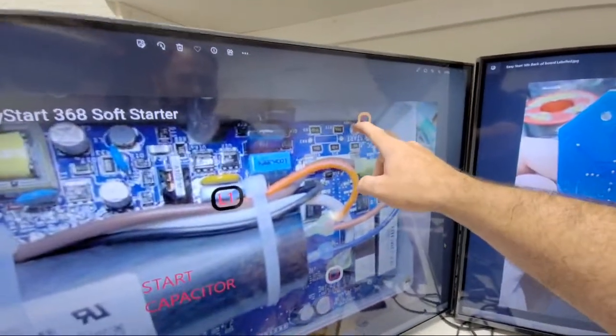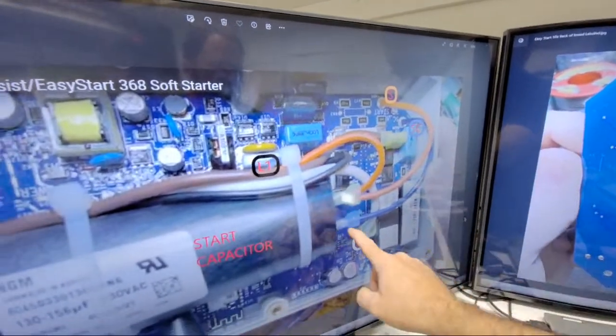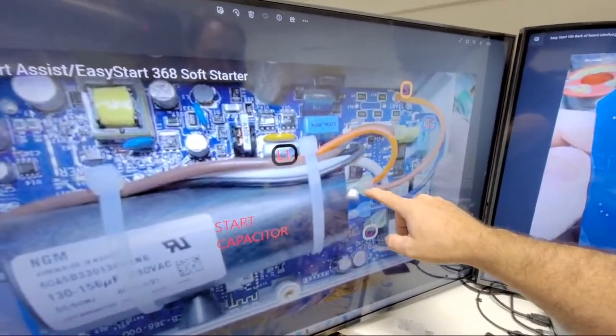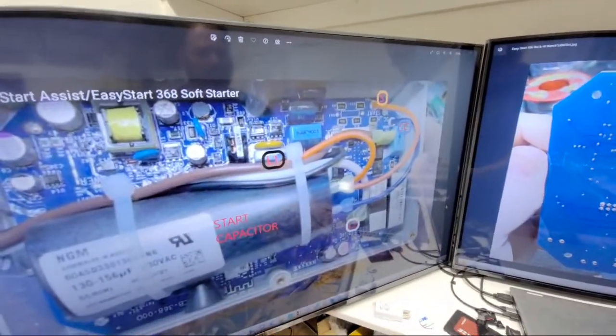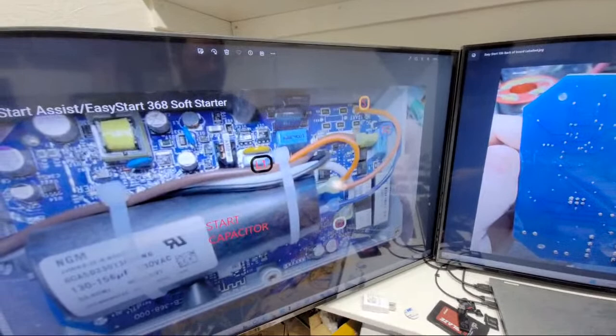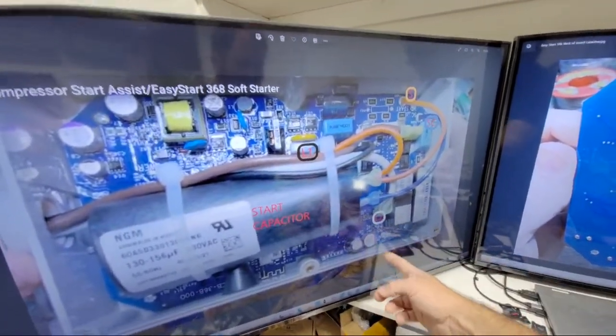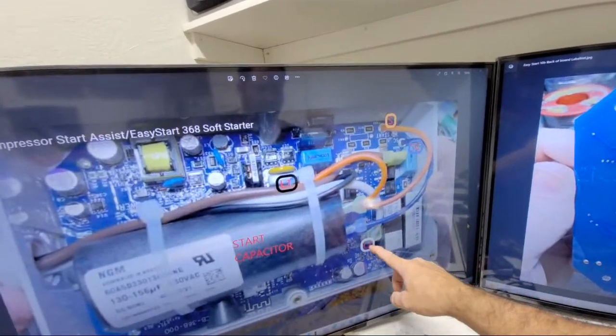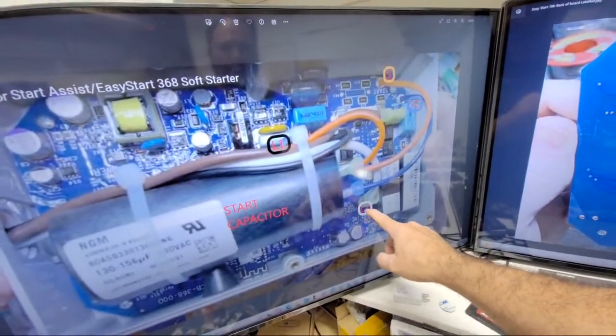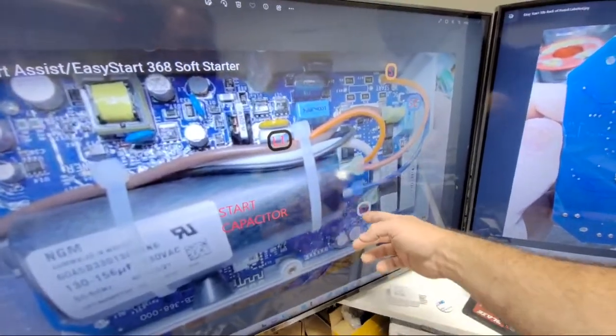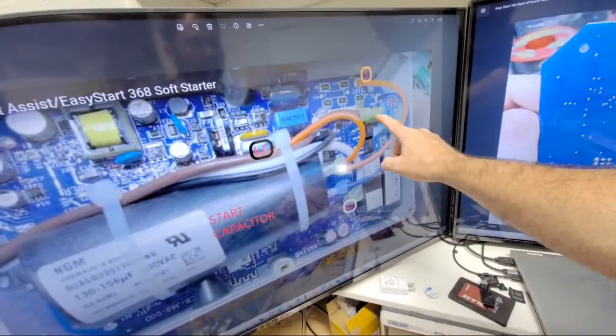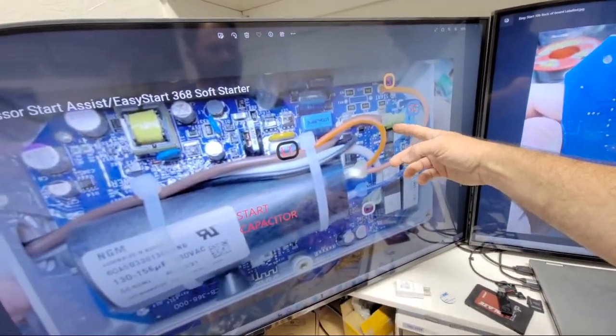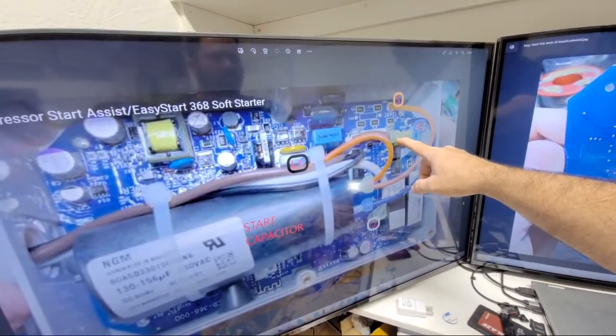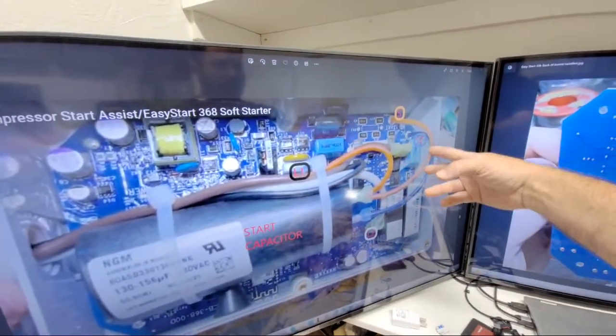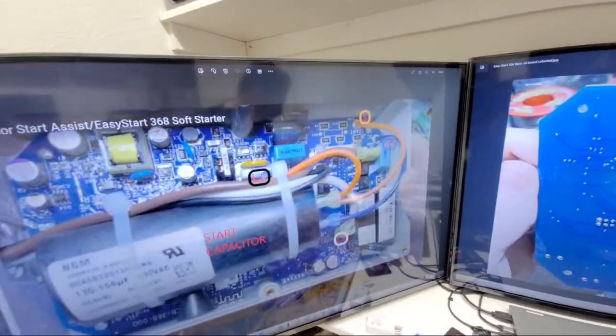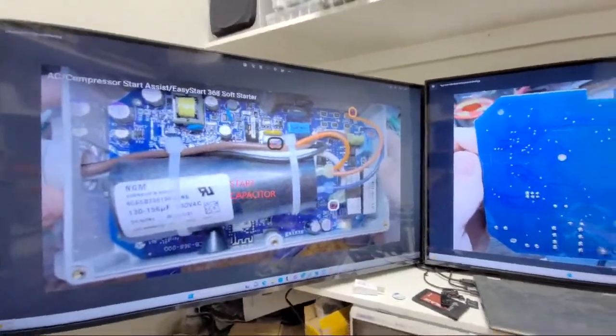And your start capacitor is here and here. This goes to one side, and this is to the other side, the common side of it, going back to your run capacitor also. So it's basically between run, which I labeled... I labeled this one wrong. This is run, L1 run, or L2 - actually I'm sorry, this is L2, this is run, I missed this label. So here's run, so this is taking run and just paralleling this capacitor between run and the other capacitor. That's what they're doing, so I missed the label on there. But they're doing some of it electronically.